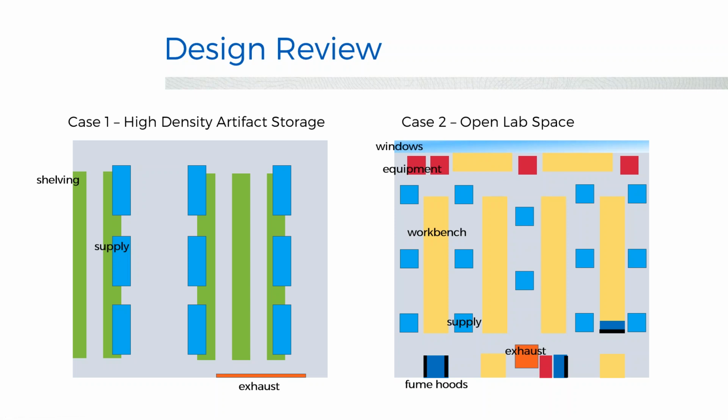So as a result of this design review, we did rework the equipment and move the fume hoods around. I believe this one was moved down to the wall over here. And some of the equipment giving off more heat was moved down closer to the exhaust, although it had an annex down here, which I didn't show, which was helpful. With regards to supplying near the windows, it turned out it was necessary, but we didn't reach that final conclusion until after running a few rounds of CFD.